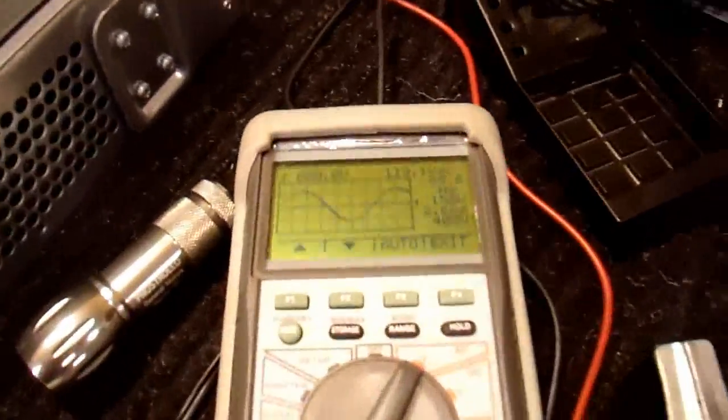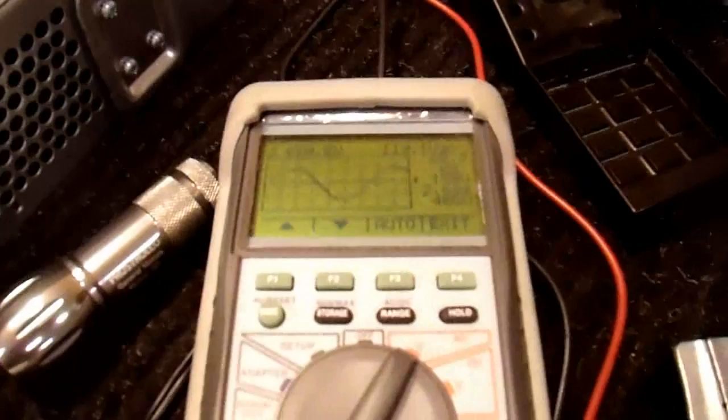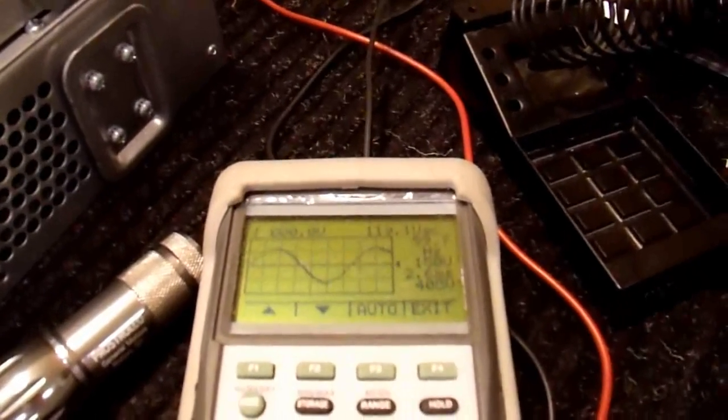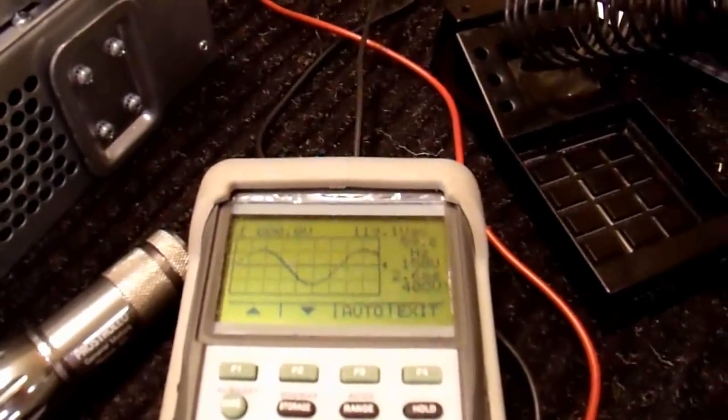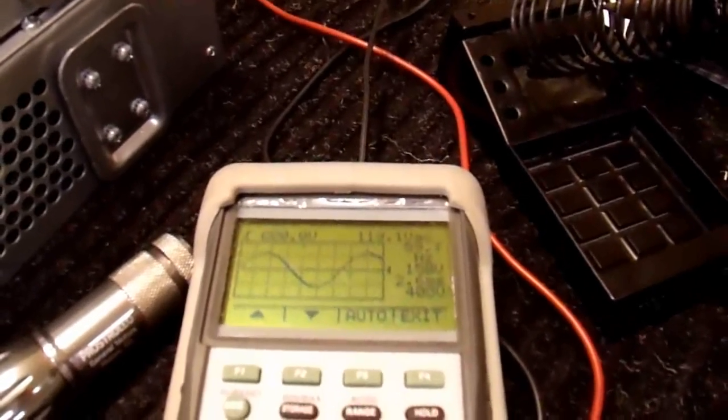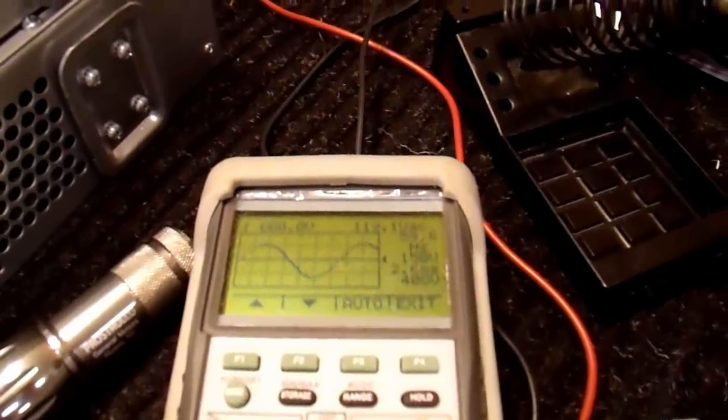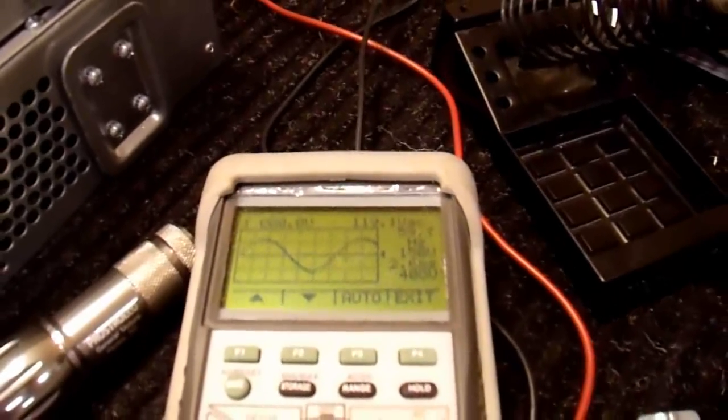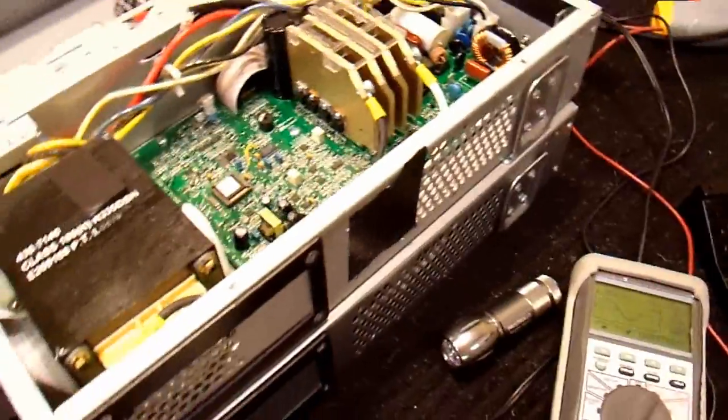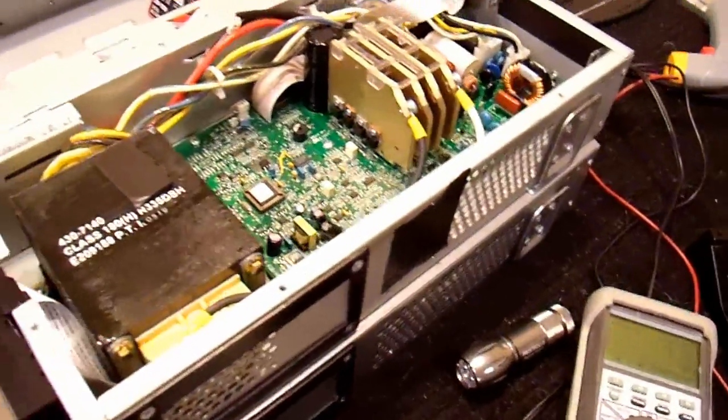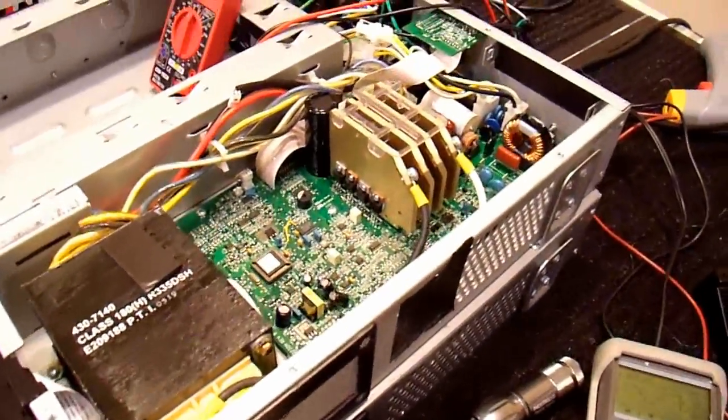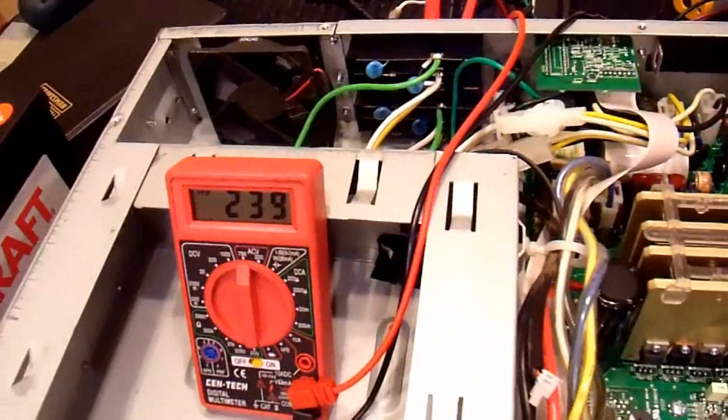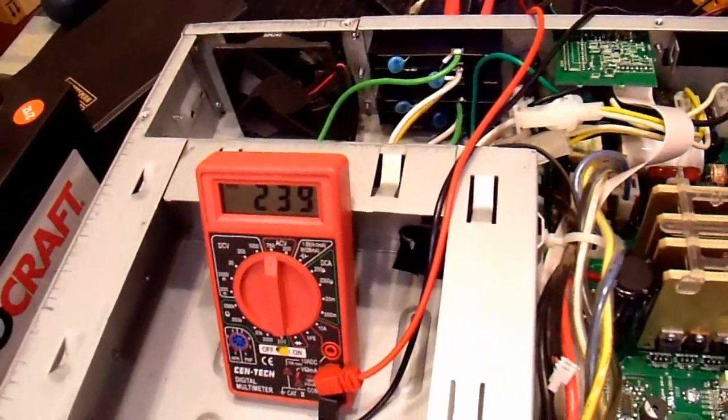And they will now output 240 volts at 3,000 watts. This is the output voltage waveform. Nice clean sine wave. I only have this monitoring one half of the phase, not the whole thing, but it is a nice clean sine wave. And I can turn this load on and off without affecting the voltage.